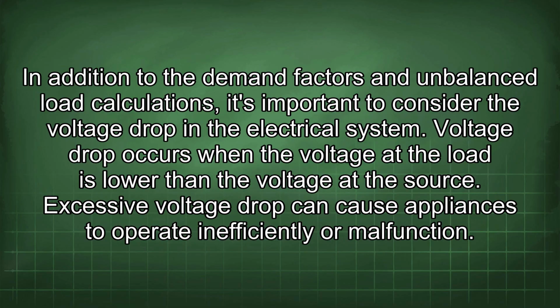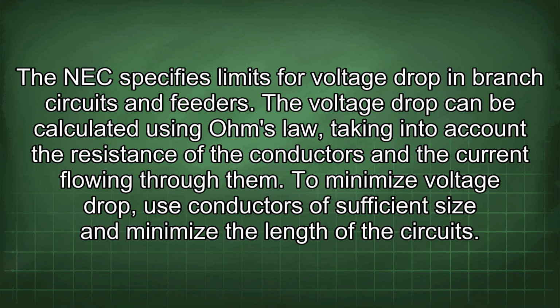In addition to the demand factors and unbalanced load calculations, it's important to consider the voltage drop in the electrical system. Voltage drop occurs when the voltage at the load is lower than the voltage at the source. Excessive voltage drop can cause appliances to operate inefficiently or malfunction. The NEC specifies limits for voltage drop in branch circuits and feeders. The voltage drop can be calculated using Ohm's law, taking into account the resistance of the conductors and the current flowing through them. To minimize voltage drop, use conductors of sufficient size and minimize the length of the circuits.